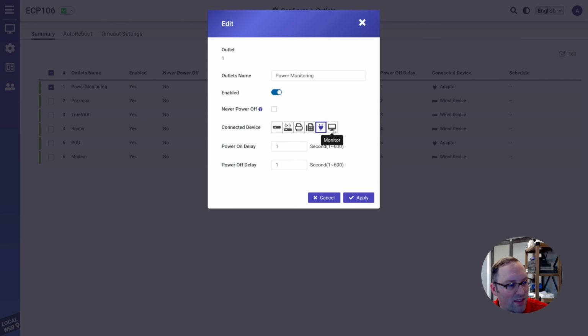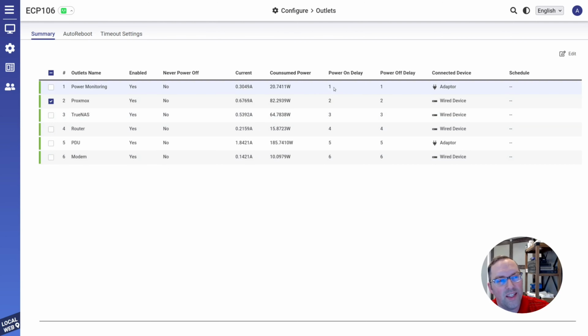Here's the power delay on and off options. You can set it to 1 second if you want—these power delays range from 1 through 6 seconds. So the last one comes on 6 seconds after the PDU is turned on, with each outlet turning on 1 second after the other until 6 seconds have elapsed and everything is turned on.